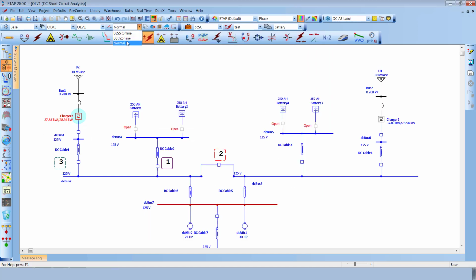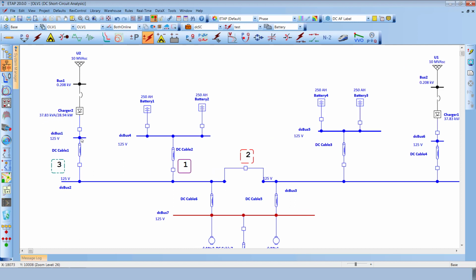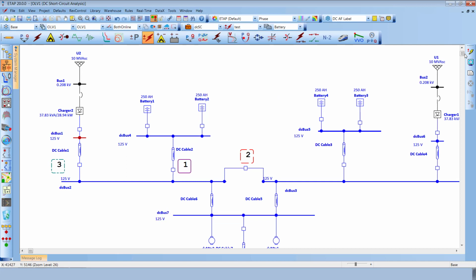So let us choose the configuration with all the sources in and start to fault at DC bus 1, where the actual short circuit terminal voltage is 0. And as you can see, the charger does contribute 150% of its rated current as the short circuit current to this particular faulted bus where the terminal voltage is 0.